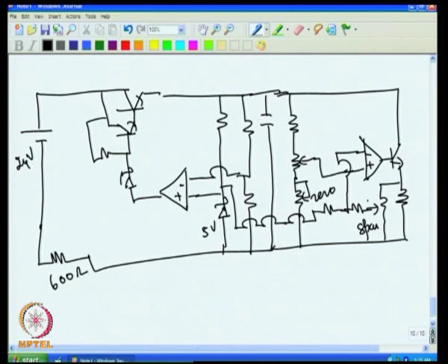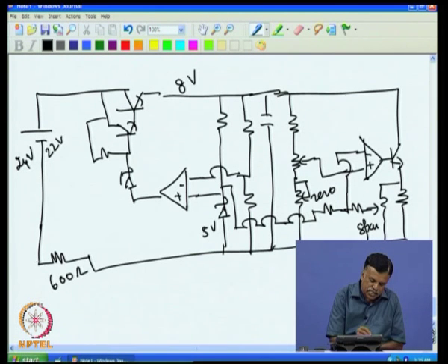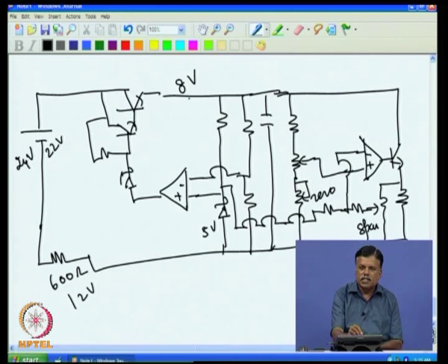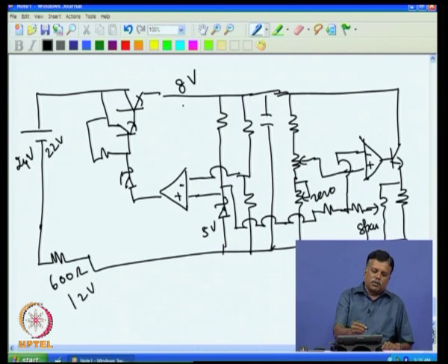That will definitely be assured, because we are keeping here only 8 volt and this is 24 volt. Even if this voltage say goes to 22 volt, and even at 20 milliampere current, which is the maximum, this will develop 12 volt only. So, out of 22 volt, 12 volt are gone across this. So, you have 10 volt left. Of these 10 volt, we are leaving 2 volt for this, and we are regulating only 8 volt.